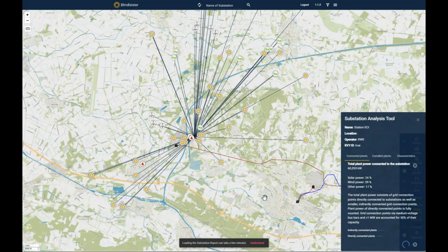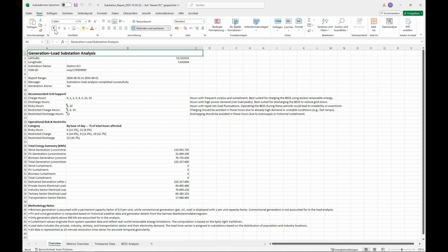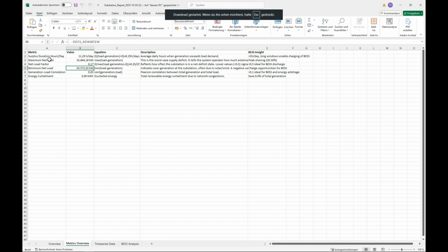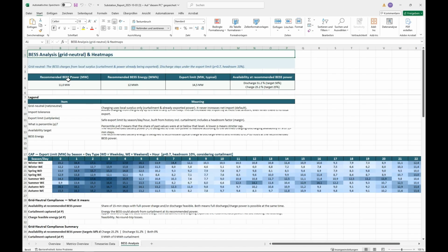We click apply and the substation report is made for us. The finished substation analysis can be seen here for this substation, and we also get a good overview of important metrics. One important metric is how long we have a surplus of generation, which is roughly 11 hours per day. We see, as said before, the load and also the minimum net load. But what is very important is the recommended BESS power. It gives us a recommendation for a battery that would fit into this network area, and also an energy, with respect to the different seasons and the different hours and the headroom, so the safety margin and the export limit that we have defined here.